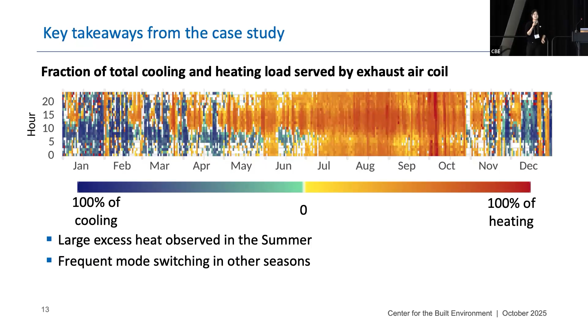So let's go over the key takeaways. The first, energy efficiency. The system achieved high coefficient of performance. This bar chart illustrates the annual distribution of simultaneous heating and cooling COP. To calculate this, we use the pure building's cooling and heating demand, excluding the exhaust air coil load, since that energy isn't usefully utilized. The building's energy use intensity is much lower than the median value for similar buildings in the same climate zone. Second, water efficiency.